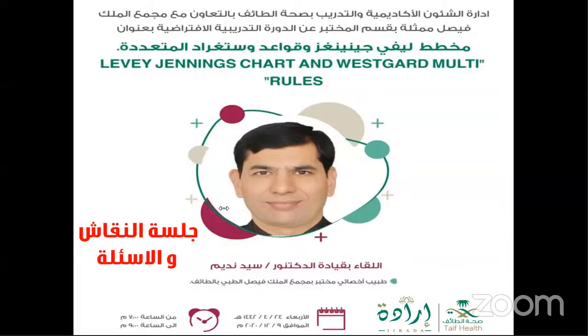I will repeat that, Walid. 4-1S means 4 consecutive results which are greater than 1 standard deviation. It has to be on the same side of the graph, and it has to be 4 consecutive results. It can be across 2 different quality control materials, but it has to be greater than 1 standard deviation. Whereas 10x means 10 consecutive results just above or below the mean. It can be within 1 standard deviation, but it is 10 consecutive results above or below the mean.